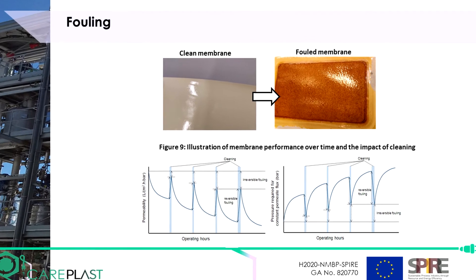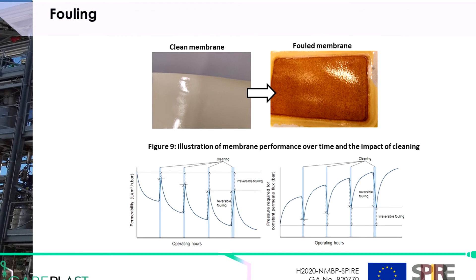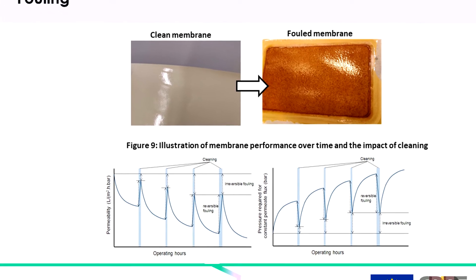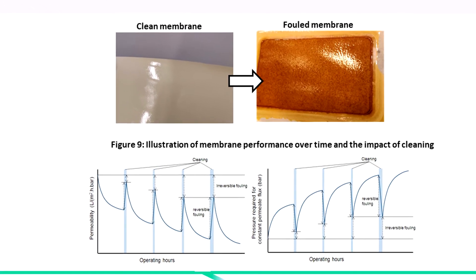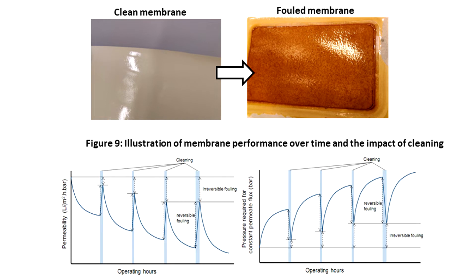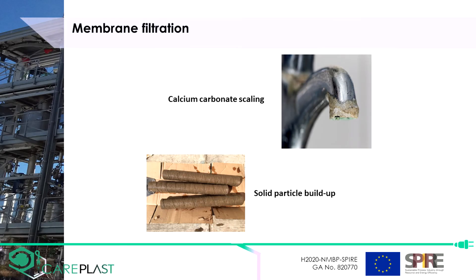During production, fouling can build up on the membrane surface, leading to a reduction of membrane performance. Cleaning is required to partially restore membrane performance. A typical example of industrial operation can be seen in Figure 9. Membrane performance will drop over time, which is partially regenerated by a cleaning procedure. General types of fouling are scaling, caused by deposits of minerals like calcium carbonate and silicon dioxide forming on the membrane surface, and particles forming a cake on the membrane surface. Scaling is often cleaned using an acidic cleaning agent.